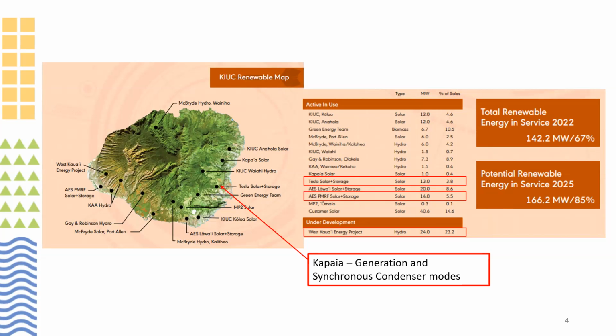Our single largest combustion turbine is over here in Kapaia, and it's actually adjacent to the Tesla. They connect basically at the same transmission bus. So we've got a Tesla virtual synchronous machine mode that we've had running there since 2018, and we dispatch that every 1 to 2 seconds. It does offer the fleet of GFM services with its inertial response.